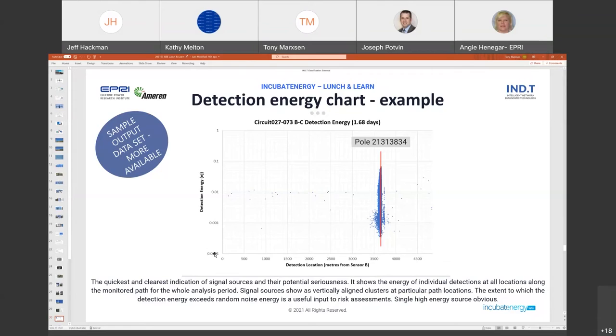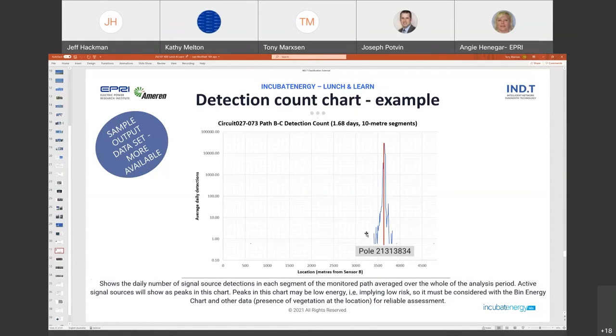You can see that's a logarithmic scale, so there's a huge range of energy, but there's a huge concentration of energy on this path, just at one pole. Here's the same data shown as a count of detections. The system measures things every second, so there's 86,400 measurements per day times three phases, about 250,000 measurements per day. This pole was generating around 30,000 detections per day, and this is only over a two-day period. So it was pretty easy to say, look, there's something there.